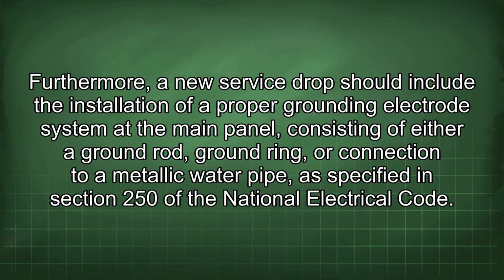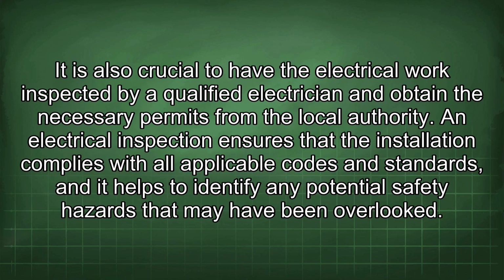Furthermore, a new service drop should include the installation of a proper grounding electrode system at the main panel, consisting of either a ground rod, ground ring, or connection to a metallic water pipe, as specified in Section 250 of the National Electrical Code. It is also crucial to have the electrical work inspected by a qualified electrician and obtain the necessary permits from the local authority.